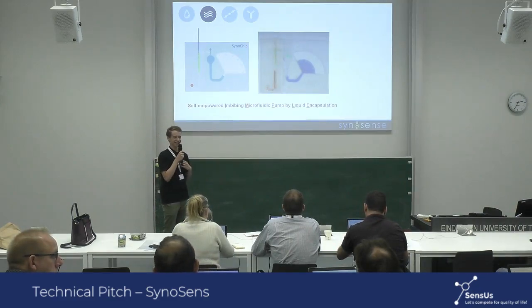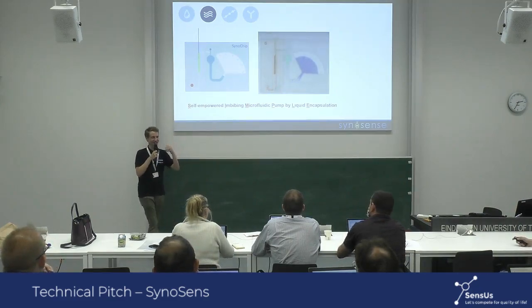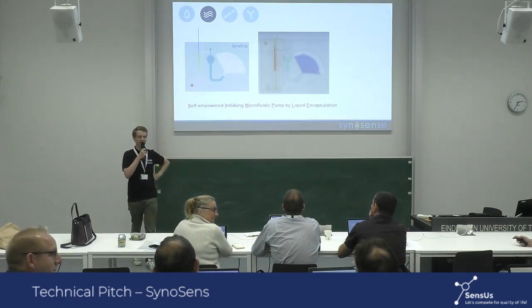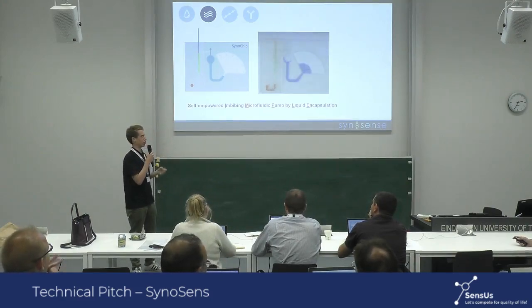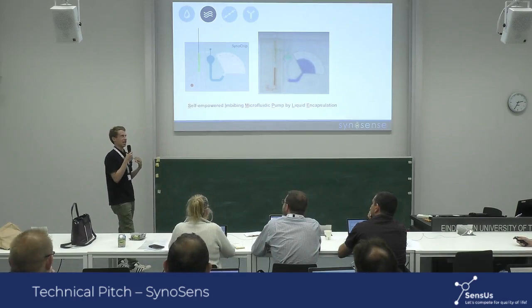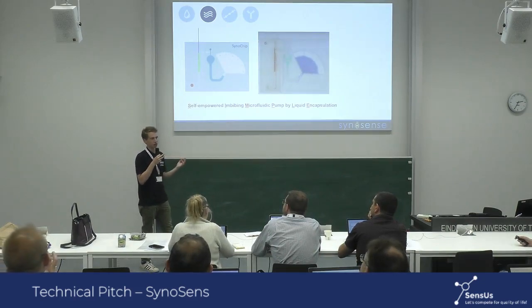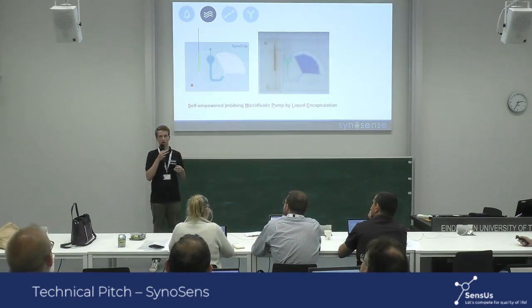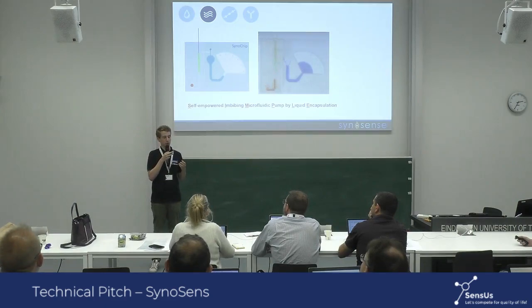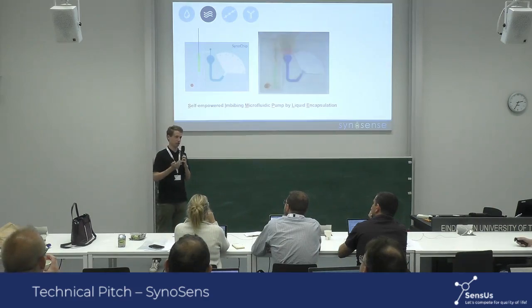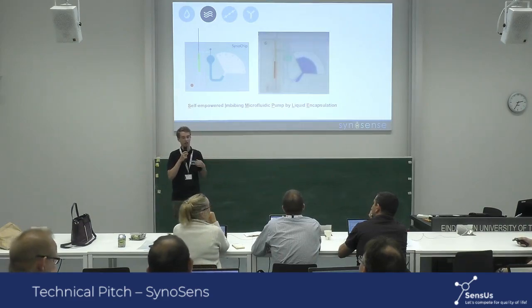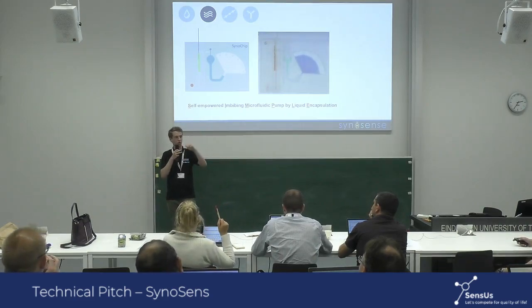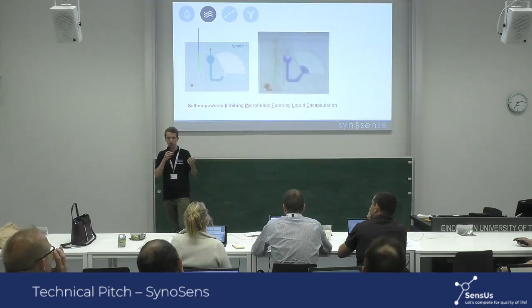That's exactly what we saw, and it's really unfortunate because we also investigated this. We actually have a high dose hook effect, so we cannot measure concentrations like 10 micrograms per ml directly, not because of the plasma, but because of the high dose hook effect. The transduced signal goes down at these high concentrations, and of course we looked at how far it goes up before it goes down, and we have to dilute 1 on 10.